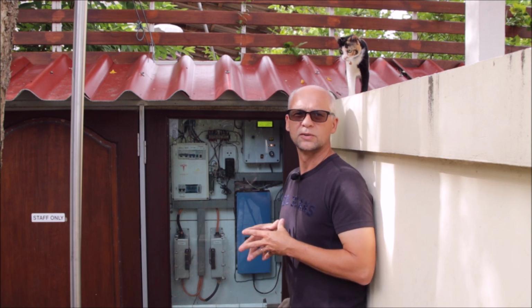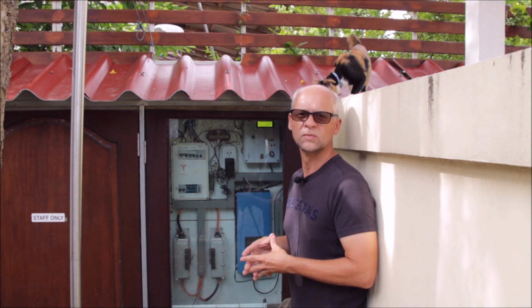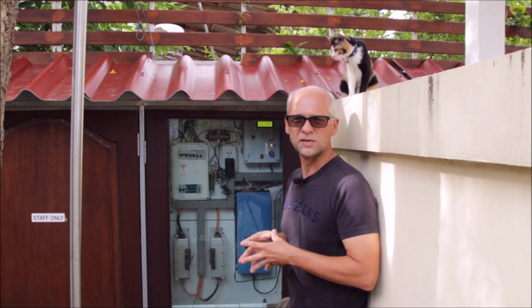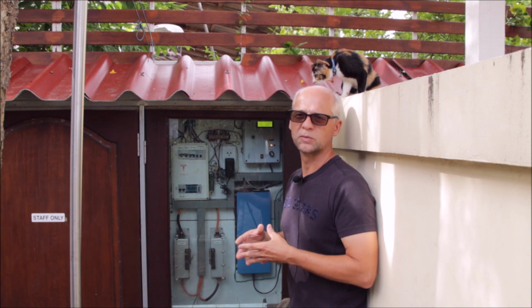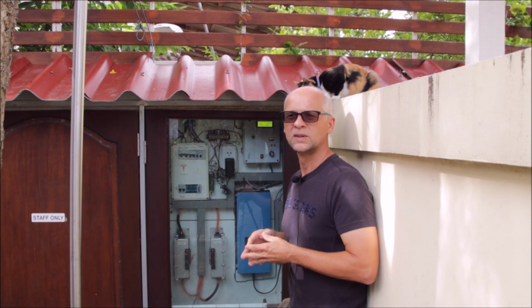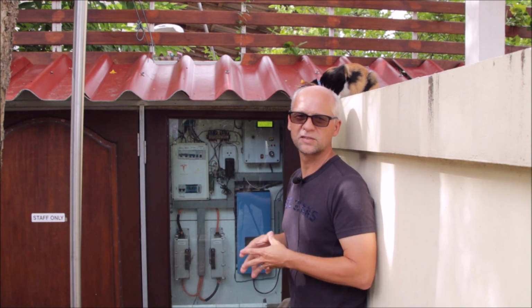So if I wanted to turn this into an off-grid style system with a hybrid inverter, I would have to replace all the equipment there. There was no demand on that phase, right? That phase there is laundry, garage and one apartment, which might have some demand during the daytime, but during the nighttime it was more or less demand only by one guest apartment, and that's not enough.